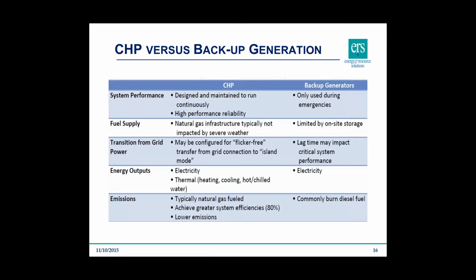As I said, you can think of combined heat and power cogeneration plants as sort of a generator plus. Here, we're just comparing the advantages of both technologies. From a system performance level, backup generators are an expensive asset that are never really utilized, whereas a CHP system is designed and maintained to run 24/7, so it has extremely high performance reliability, and it's also providing significant savings every minute of the day.